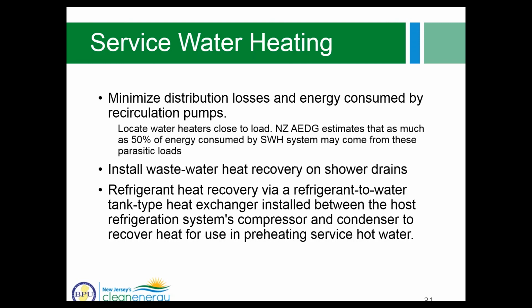Another opportunity is to install wastewater heat recovery, such as on shower drains, so that the hot water going down the drain preheats incoming water, and obviously that would only work if you have in-unit water heaters. There is also a refrigerant heat recovery option that you can use to preheat service water. And these last two bullets shown on the slide will show savings, both once the building is constructed, but also you can get credit for that when you do the energy model.